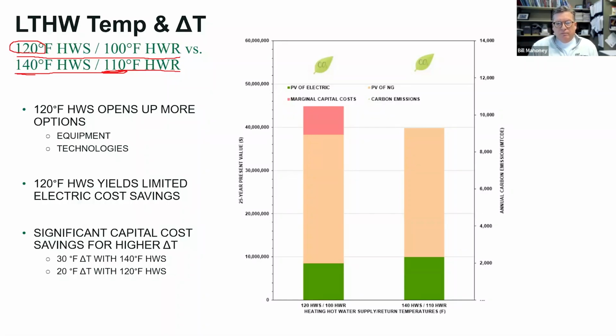So the chart here on the right shows you that this is the 120 column on the left, 140 on the right. And you can see in green that the electric energy is definitely higher for 140. This is life cycle cost. This is 25-year life cycle cost. So yes, I'm going to pay more every hour, but in 25 years, here's what it relatively adds up to. The next tier here is the gas usage, and that's kind of a wash. You're going to get a little more capacity probably out of the 120 system. So this column might be a little bit shorter, but they're pretty equivalent.